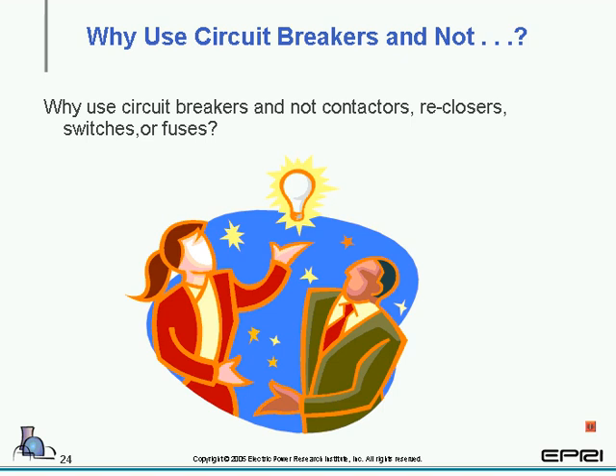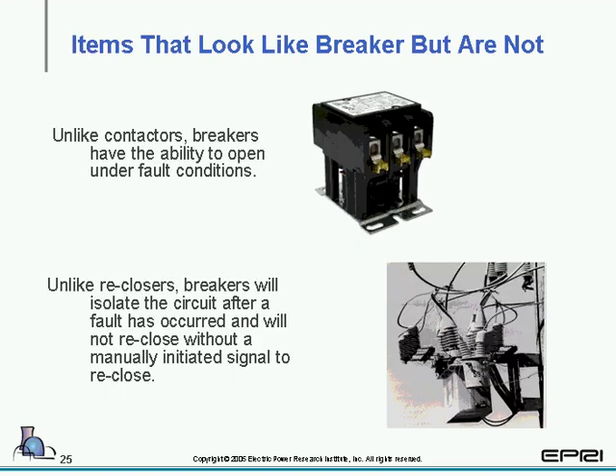All right, moving on, we're going to take a look at some things that look like breakers but are not, and why we use breakers, not contactors, reclosers, switches, and fuses. First thing we're going to look at is a contactor. Unlike contactors, breakers have the ability to open under fault conditions. If a contactor opens even once under greater load than it is rated for, it could fail.